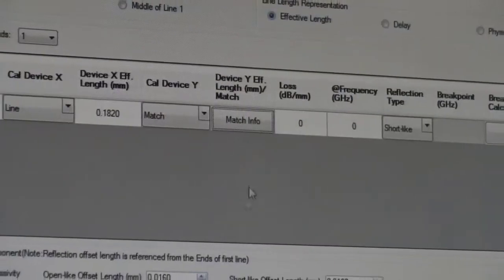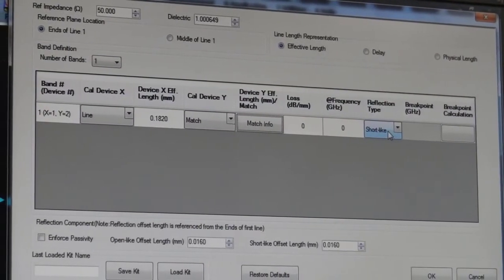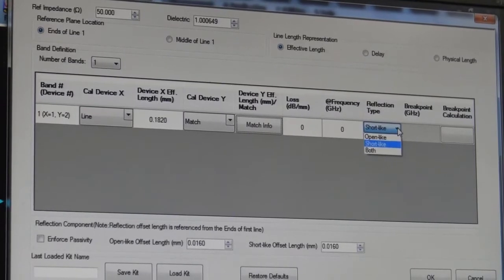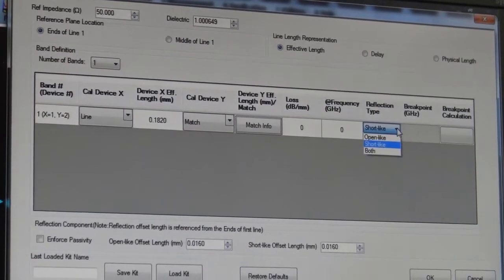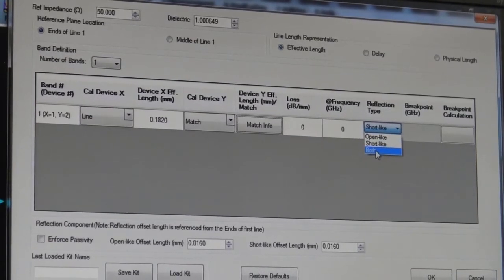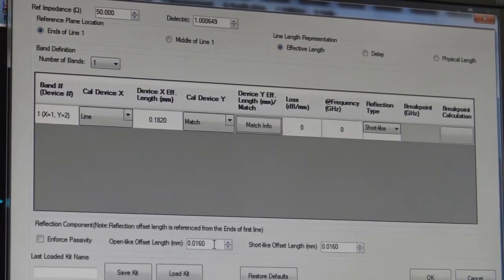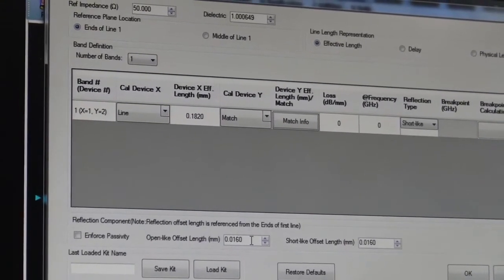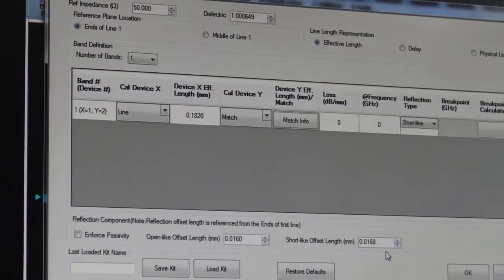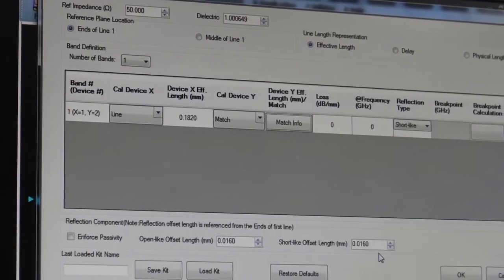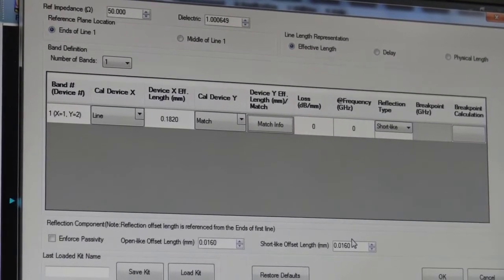All right, so now our match is defined properly, and we just now want to determine what type of reflect that we're going to use, either an open or a short. It doesn't have to be perfect, it's just an open like or short like. You can also include both, so you can include two different reflection types. That's our advanced LRM capability. In this case, we'll just be doing the short. And now to finalize the description of the standards we're using, we can enter the offset lengths for the open and the short. And in this case, it's 16 micron length to the shorts and the opens, and that's what's entered here. And so now we're set up.